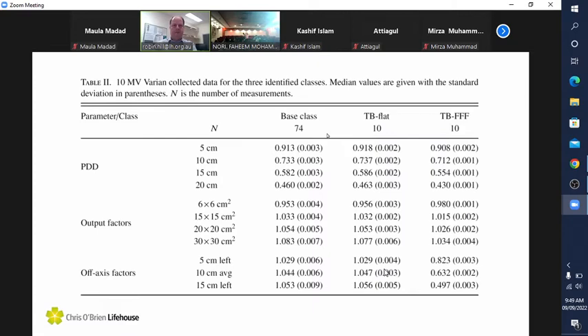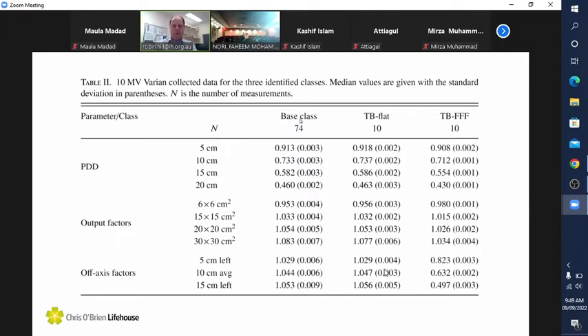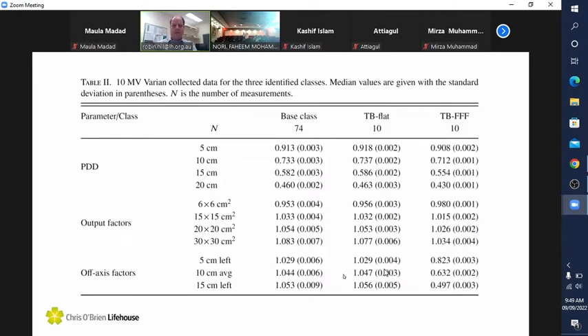For example, this is the 10 MV and the PDD values at a range of depths for 10 by 10. They've got output factors. I will admit these are not small field size factors, but it gives you an indication of what they are collecting.